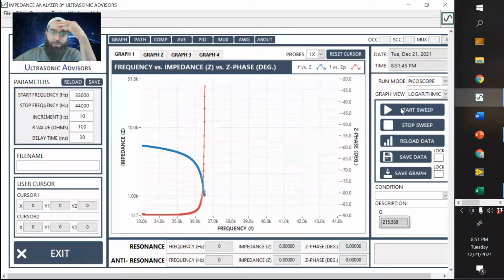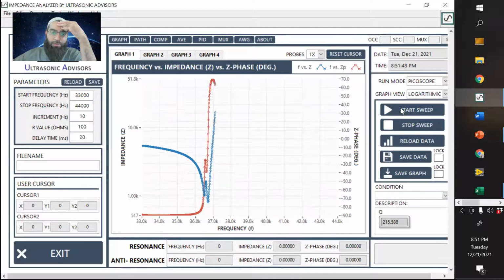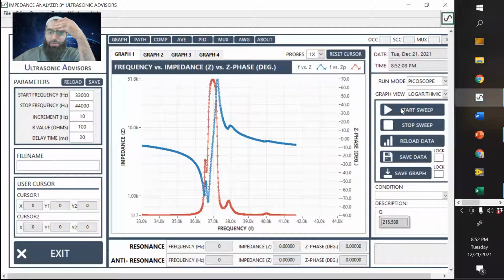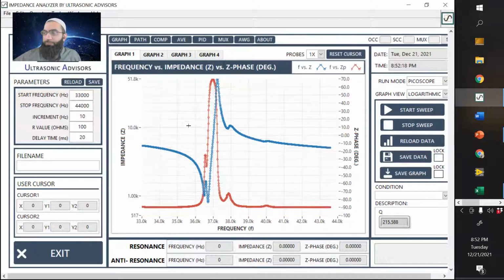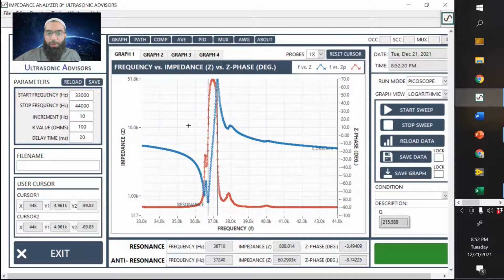This is actually what I wanted to show. I saw this earlier. When the tip is loaded, those two frequencies kind of merge together, which is nice because now you have a single operating point. Those frequencies won't really get too confused with each other. Now the power delivery may change, and that may have to do with the design of the transducer. This resonant frequency mode seemed to have really taken a hit and went downward or got damped out completely. It may not work here.